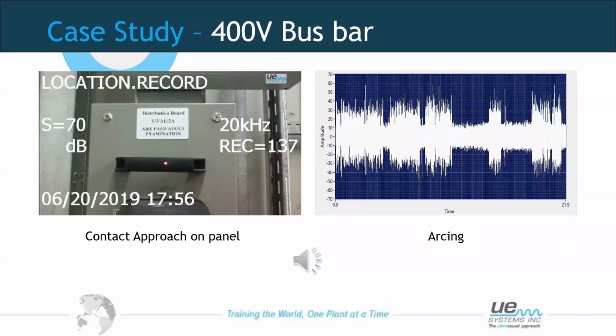So again, there's no moving parts inside this asset, within this cabinet, so we shouldn't expect to hear any sound. We hear quite strong discharges occurring there, which is an indication to me that there is arcing occurring within that cabinet. So that would mean, would I want to open that cabinet with that live? Again, a great indication of doing something safely.